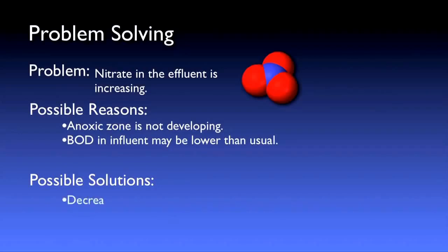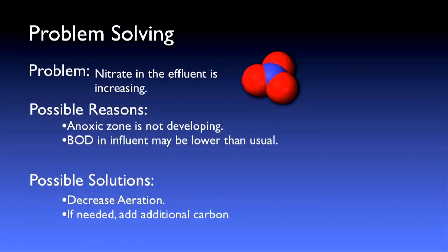If the BOD loading is unusually low, there may not be enough carbon for the denitrifying bacteria to perform. This less likely scenario would require additional carbon to be added to the influent stream.